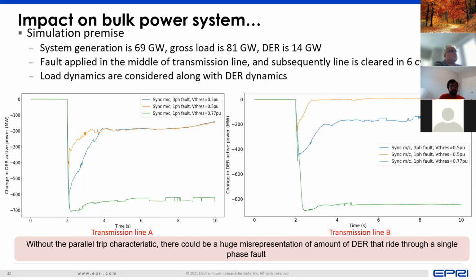In some cases, it may actually show that no DER trips at all for a different line. But if you actually parameterize the model appropriately to represent the single phase tripping characteristic, then it would actually show you more DER tripping, which is what a transmission planner needs to see. So say in this case a transmission planner applied this fault and saw that, oh, okay, for the single phase event, no DER trips, which means they're all good. But in reality, for the same single phase event, close to 800 megawatt of DER could have tripped across the entire network. And the transmission planner needs to be able to see this tripping occurring so that they can plan for this. So that's where parameterization also plays a role.